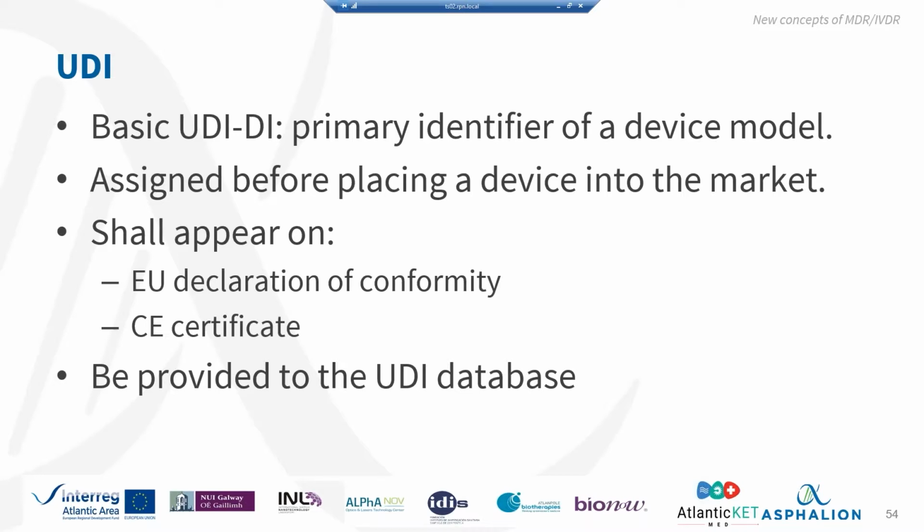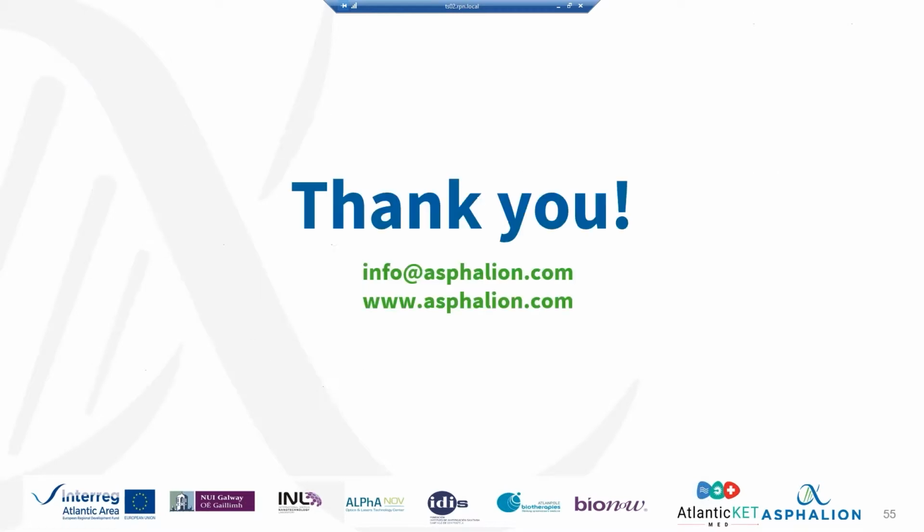Well, this basic UDI-DI has to be there. It's got to be easy to identify the device. And obviously, as we were saying, it's got to be provided to the UDI database, integrated in EUDAMED.